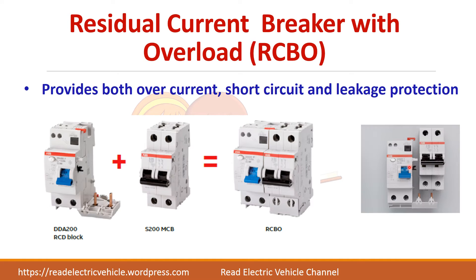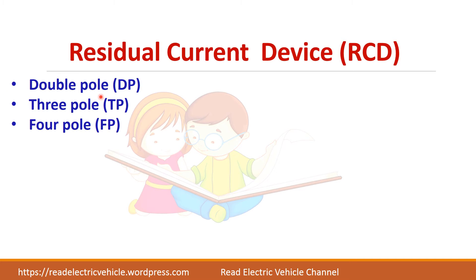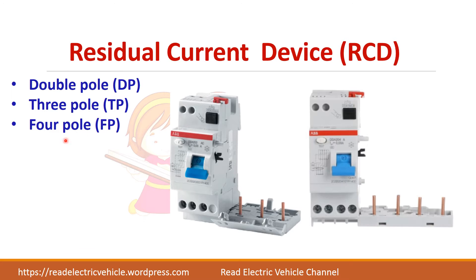An RCD block, when you insert an MCB, will look like this. So an RCD plus MCB block combined together will give you the RCBO function. You have to find a compatible MCB for that particular RCD block. RCD devices are available either as double pole, triple pole, or four pole, and depending on that you choose your MCB and connect it.